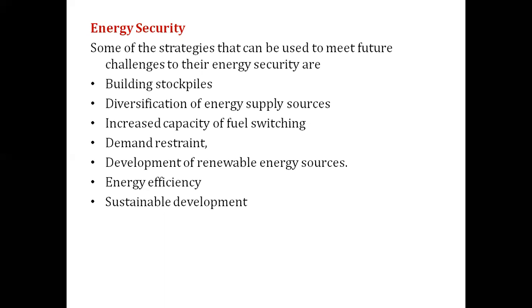But we can build some stockpiles. Suppose there is a chilling plant in some factory. It is not necessary to run it 24 hours. You can run the chilling plant at night during the off-peak period, from 10 p.m. to morning 6 or 9 a.m., and shut it down during the day. So in the off-peak period you are storing energy in the form of cooling energy, and during the daytime when maximum demand occurs, you shut it down, or run it in most periods but shut off during the peak period from 6 p.m. to 10 p.m., when it is not necessary to run. This is a kind of stockpile.